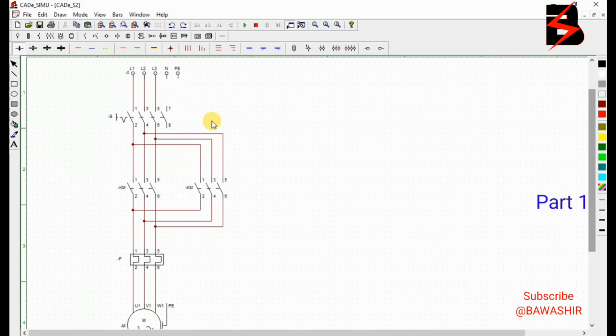As I told you, it is not that you only have to interchange line 1 and 2. No, I mean 2 and 3. But you can interchange 1 and 3, you can interchange 1 and 2, you can interchange 2 and 3. Any 2 changes the direction of rotation. But contactor 1 keeps the lines in their respective order.